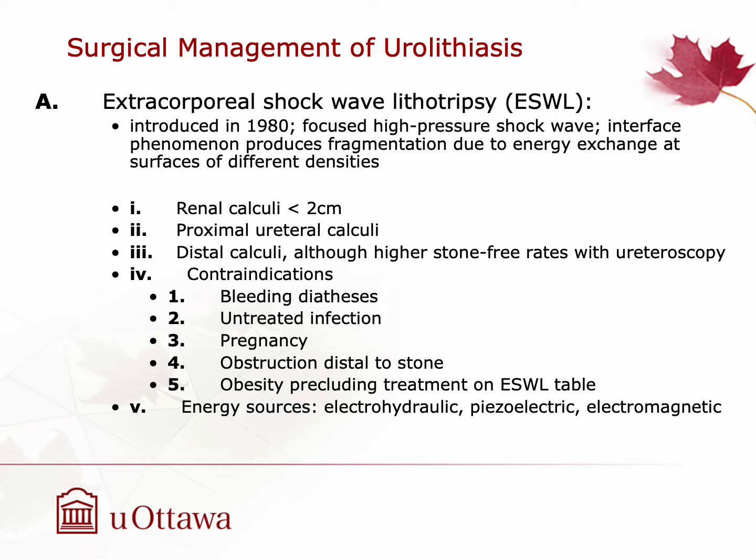Some of the contraindications why we can't perform ESWL: if a patient has an untreated bleeding diathesis, or if there's untreated infection. Pregnancy is an absolute contraindication to the use of shockwave lithotripsy. And obviously, if there are obstructions distal to the stone, such that the fragments will not pass out, then we have to look at other methods of intervention.